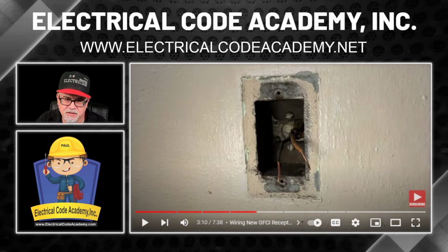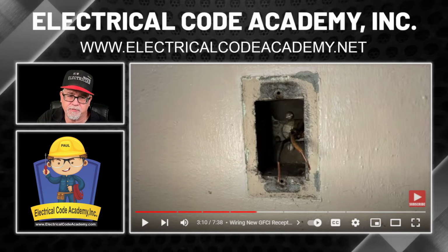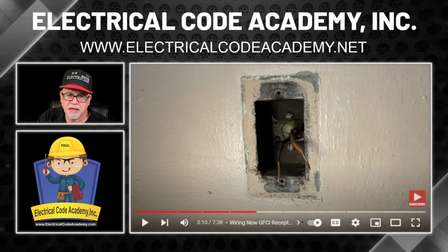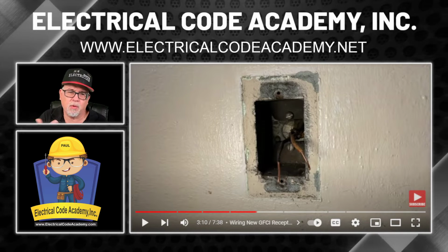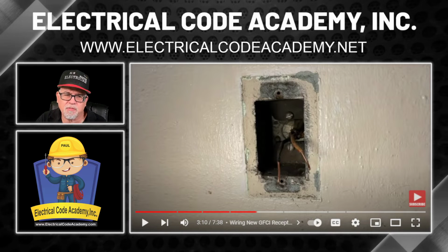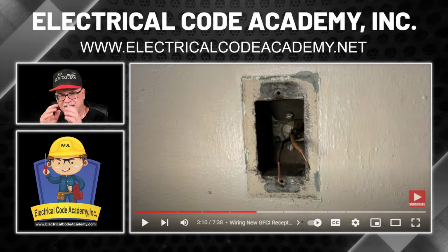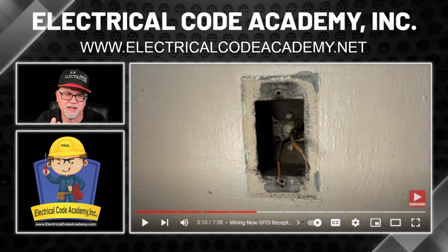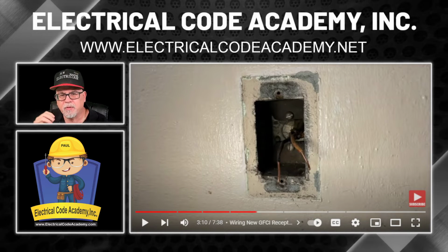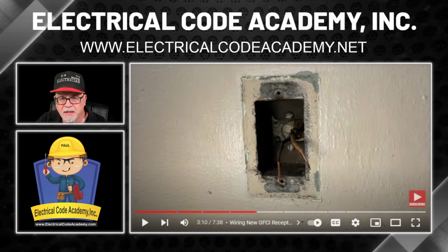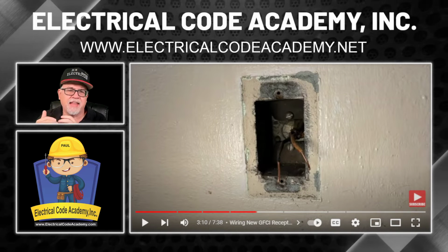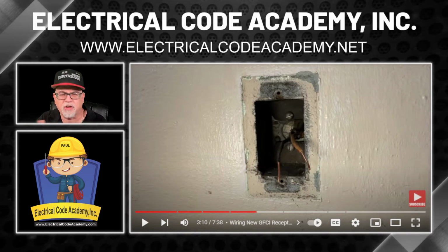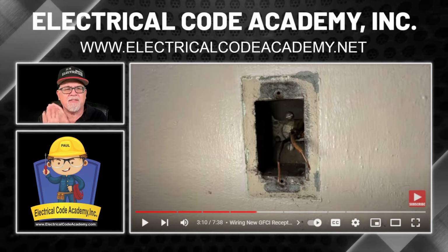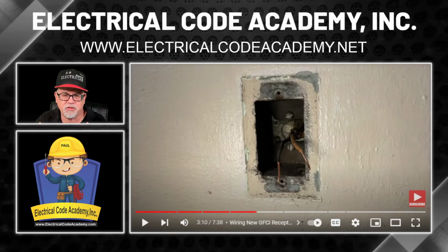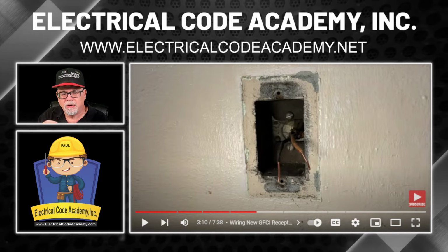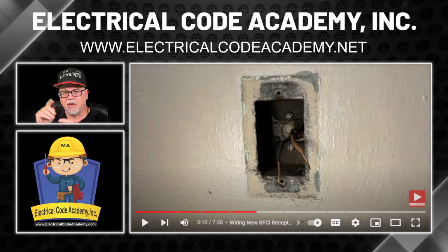One of the things that I like to do is, if I were to cut off the receptacle like that, or if the ends were too damaged and I wanted to replace it, then what I would do is splice on pigtails so that I could take that older, probably a cloth type of insulation, really old, and I can train that back into the back of the box. And that way I'm not tugging and pulling on any of that cloth or whatever. It's probably brittle or might crack off. For me, I want to have less stress on that. I don't want problems that an electrician has to come back and deal with. So I would splice on my pigtails of the fresh new wire.